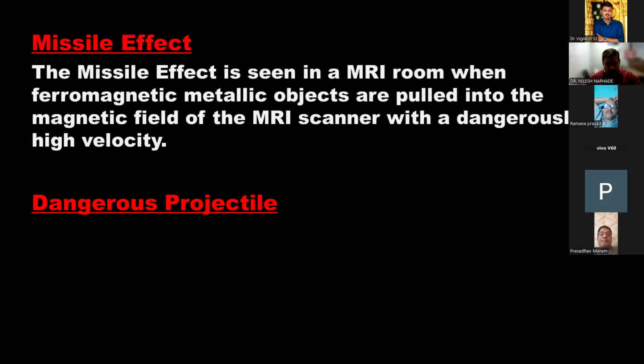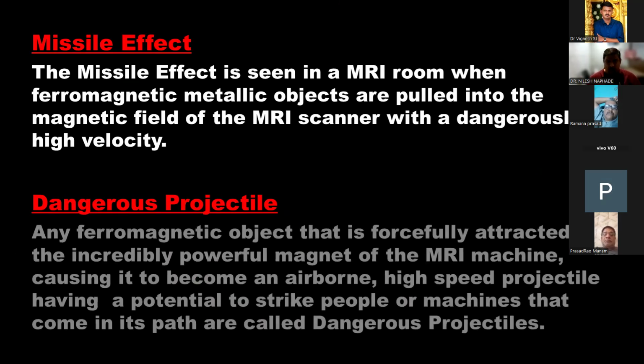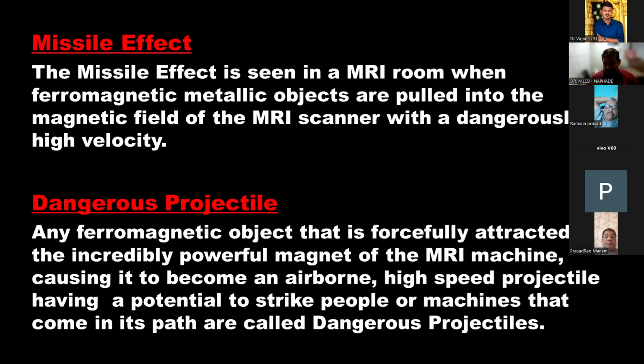This is what I'm going to tell you: two effects. Missile effect and dangerous projectile effect. These are universal terms used all over the world. What is a missile effect? Please, all the people listening to me, focus on the words. The missile effect is seen in an MRI room when ferromagnetic metallic objects are pulled into the magnetic field of the MRI scanner with a dangerously high velocity. This effect of a ferromagnetic substance being pulled is called missile effect. And the object which is pulled becomes a dangerous projectile.